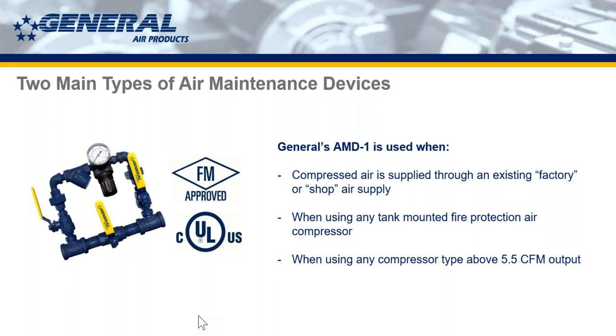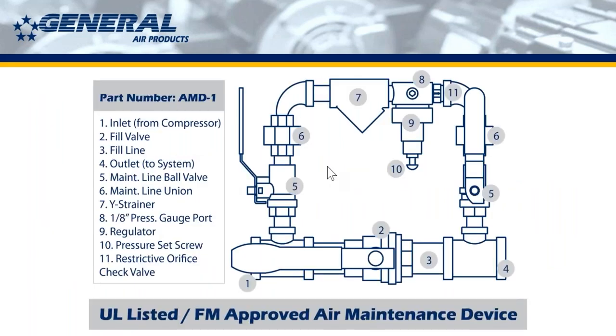But that said, you can have a smaller fire protection air compressor that puts out less than 5.5 CFM. And at that point, if it's a tank-mounted unit, you still need the AMD1 air maintenance device with the air regulator. There we are. So here's a parts breakdown. Inlet and outlet 1 and 4, that's the fill line. 2 represents the fill valve, 3 is the fill line. Inlet and outlet 1 and 4.